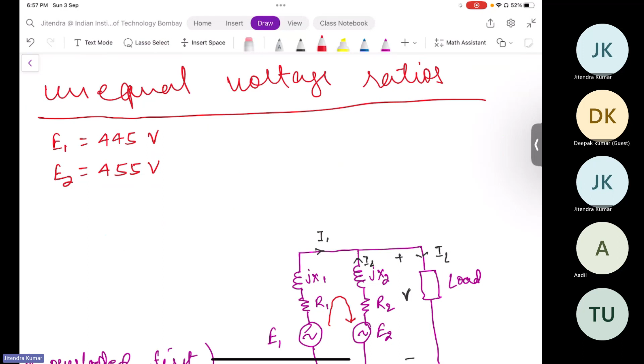Now there will be some circulating current at load or no load, because there is a difference between E1 and E2, and that circulating current will be high since these are leakage impedances and both are small quantities in the denominator. Let me compute this circulating current: it will be E1 minus E2 divided by Z1 plus Z2. These impedances are very small, and not very high either. So basically the circulating current will increase, leading to copper losses and a reduction in the contribution of kVA rating to the load.